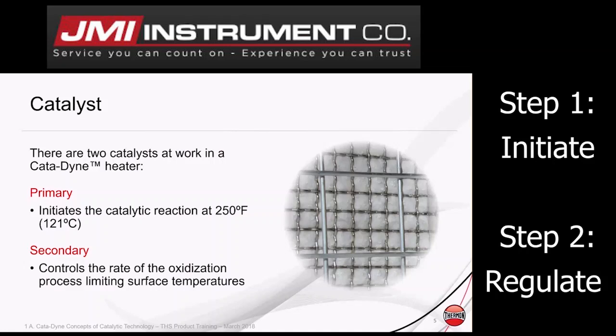That 250 Fahrenheit temperature is the preheat temperature — or the pre-start temperature — that needs to be achieved before we can really initiate the full flow of gas into the heater and then ramping up the temperature to the full operating temperature of 750 to 800 degrees Fahrenheit.